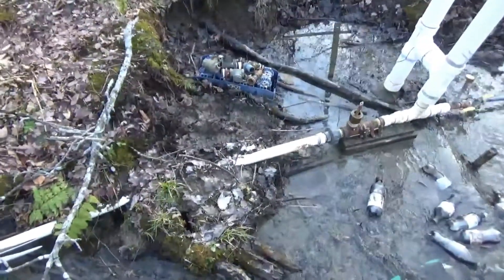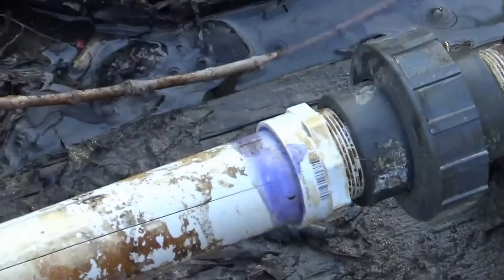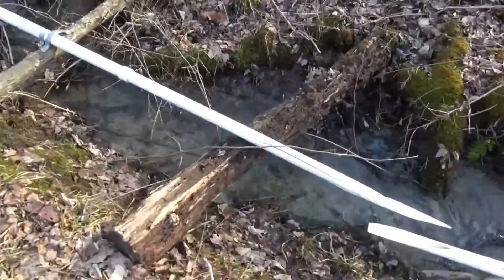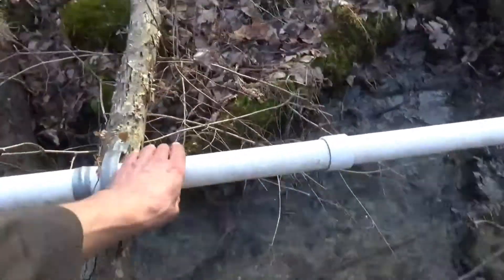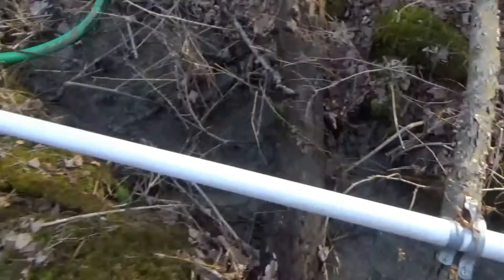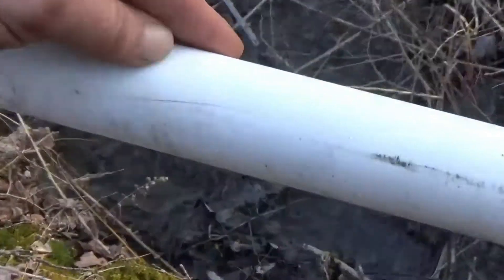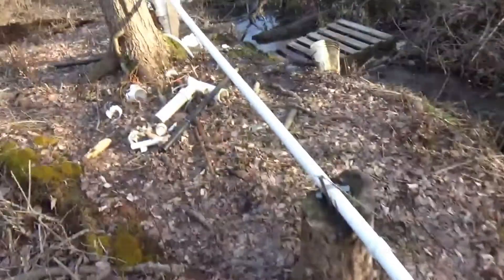Let's work our way back up the line. Obviously the drive line split. You can see that crack starting right there at the head, and it runs right on up — you can see it actually completely split open up here. There's still crack here, there's still crack there. So basically the entire drive pipe split open.